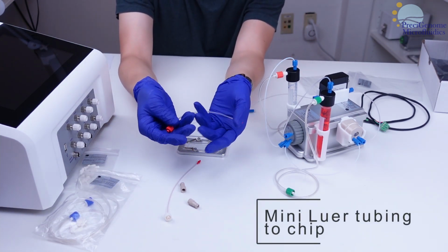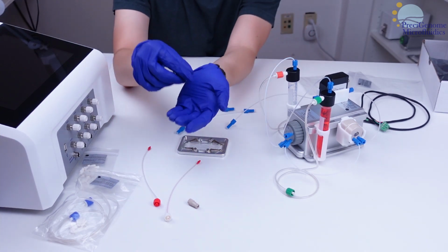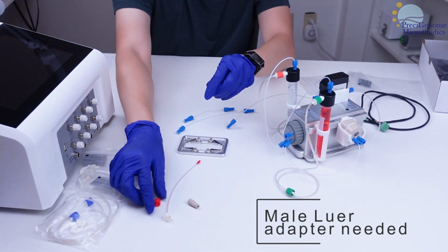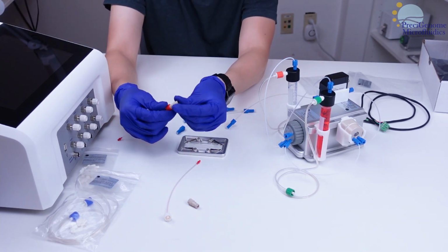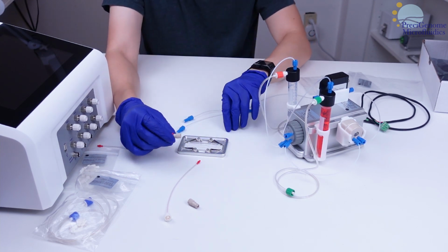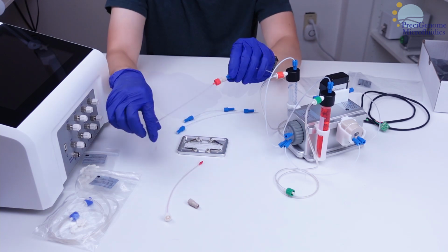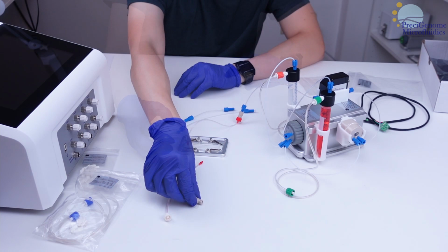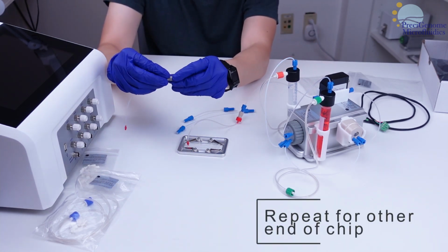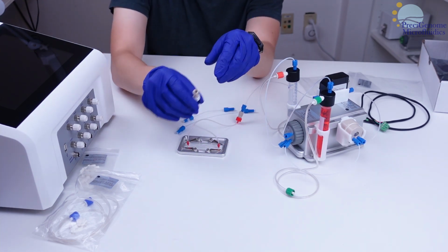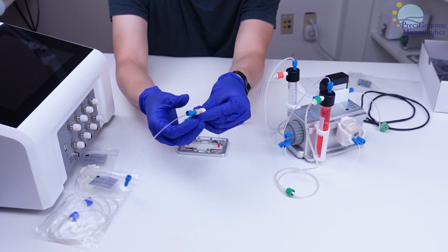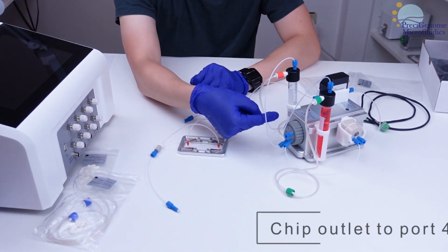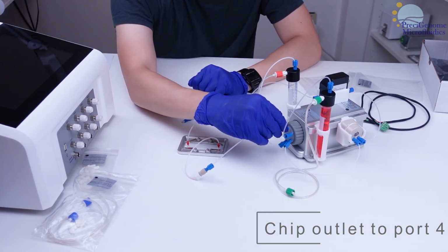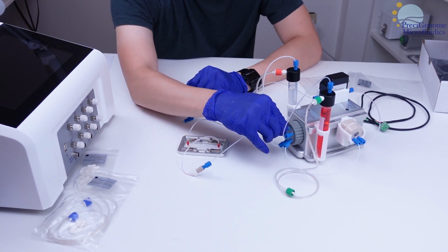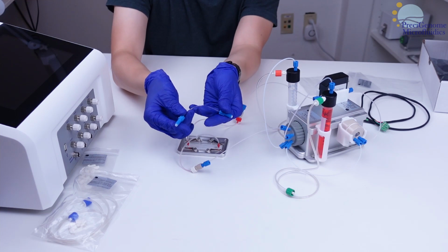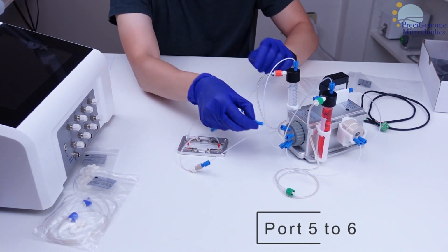The mini Luer tubing goes straight into this chip, but a male Luer adapter is needed to connect it back to the PTFE tubing. Assemble this tubing and connect to either end of the chip. Repeat this process for the other end of the chip. Ensure both ends are part of the same channel. Connect the chip outlet tubing to port 4 of the rotary valve. Finally, connect ports 5 and 6 on the rotary valve to each other.